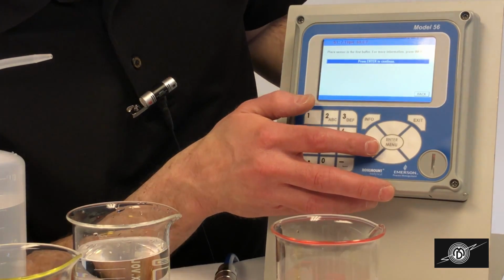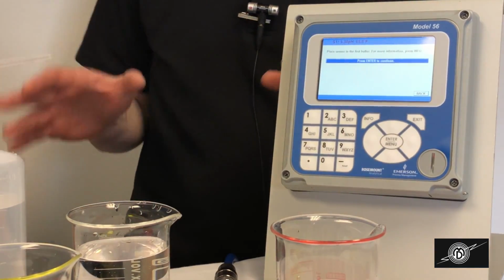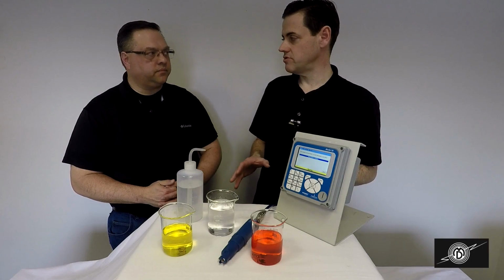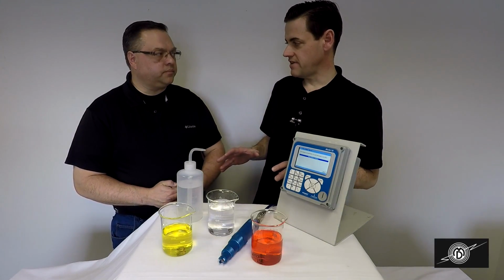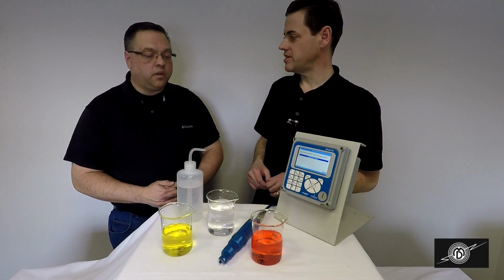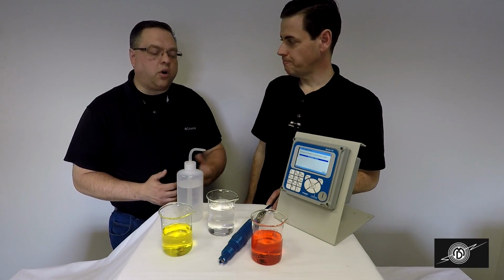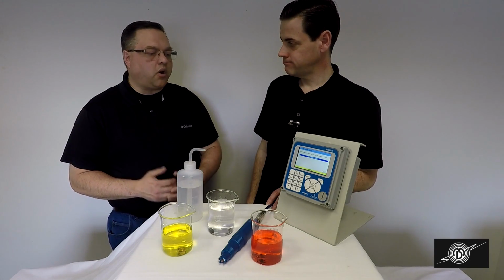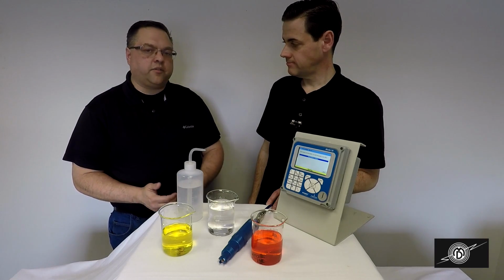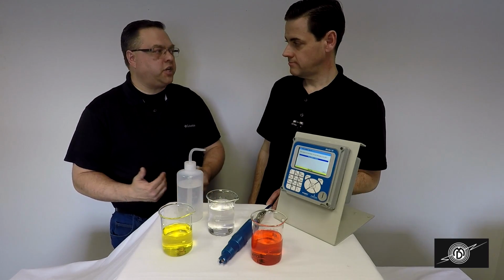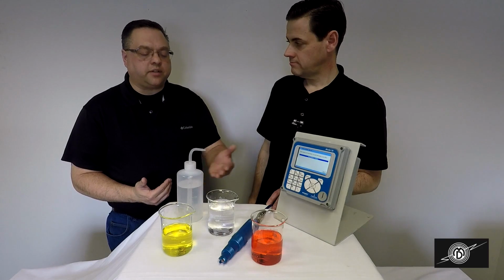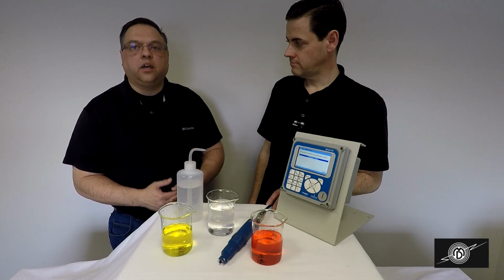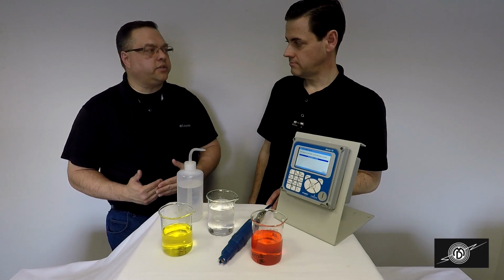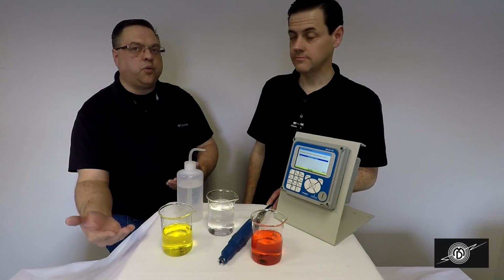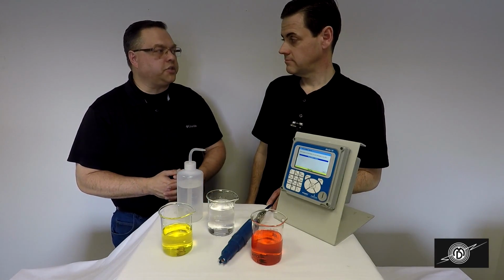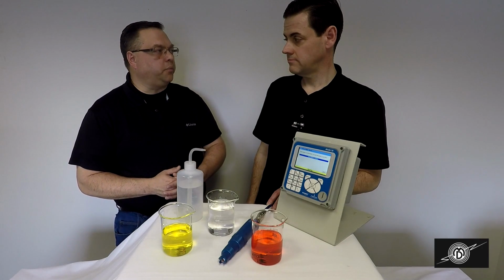Go into our calibration mode. Another question before we begin, temperature. There's a lot of talk about temperature and pH. What kind of effect, if any, does temperature have on pH measurement? Temperature has a big effect because all of our online pH sensors are temperature compensated. Therefore, the readings are affected by changes. Each sensor has a temperature sensor built within the body. You need to let that sensor come down to the same temperature as your buffer. Otherwise, you're going to give yourself an unstable calibration and it will give you erratic readings while in process.